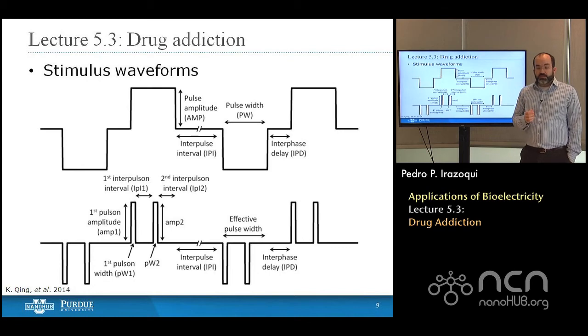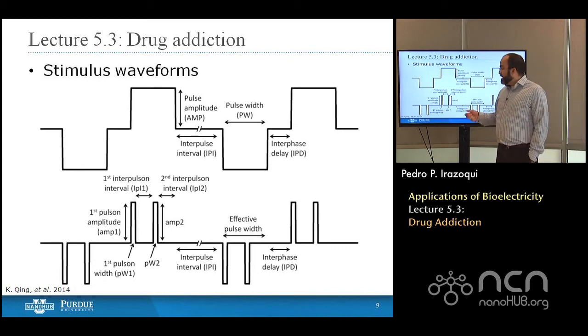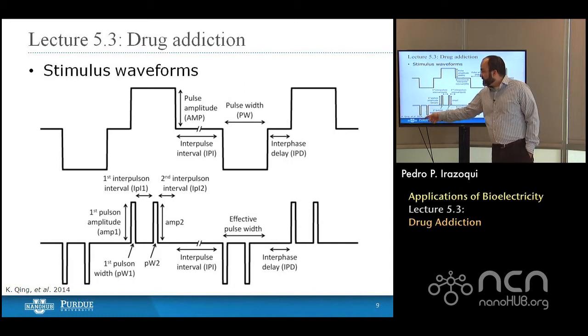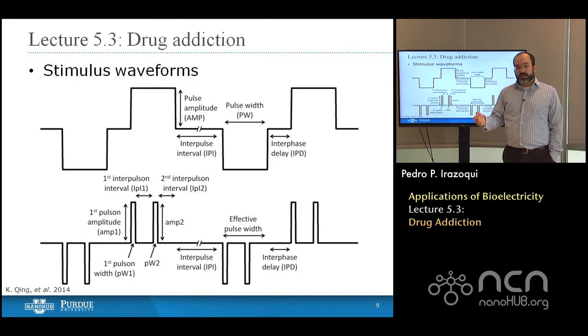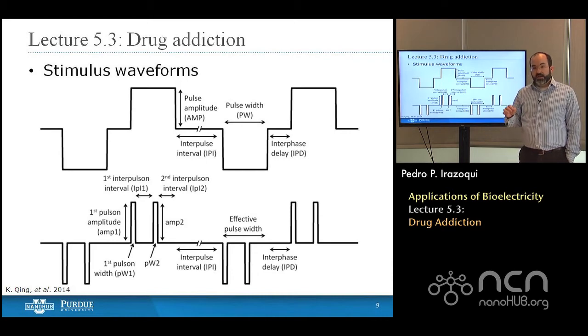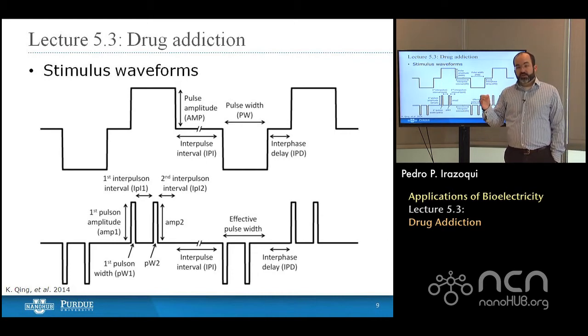First of all, hopefully, it would achieve an improved physiological response. And second of all, it would do so with less current. So if you integrate the area under the curve, you'll find that you have less current being delivered for the pulsons than you do for the square pulse. So you have a smaller dose, which means that you're going to have less desensitization of the brain. You're going to have less electrodeposition of the electrode material into the brain when you stimulate, even though it's biphasic.